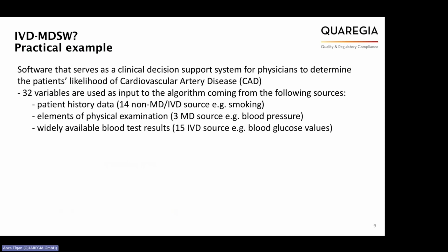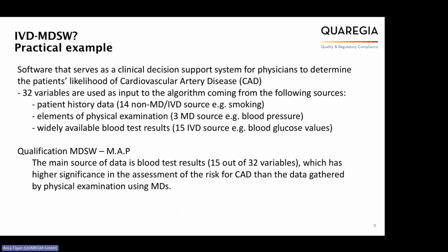So first of all, what we have to do, as we have seen, is to qualify the medical device software or the software itself to see if it's an IVD MDSW. So first, let's qualify it if it is an MDSW. Does it have a medical purpose? Yes, it does. Does it perform an action on data that is different than archival or simple search? Yes. And is it for the benefit of individual patients? Yes.